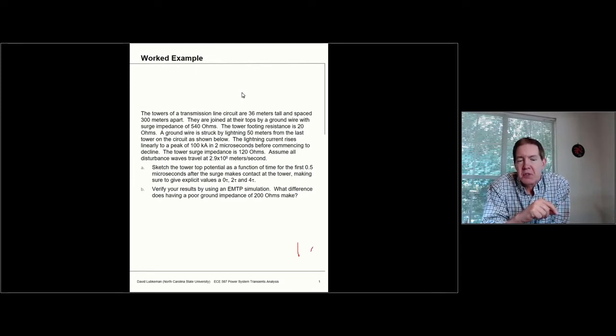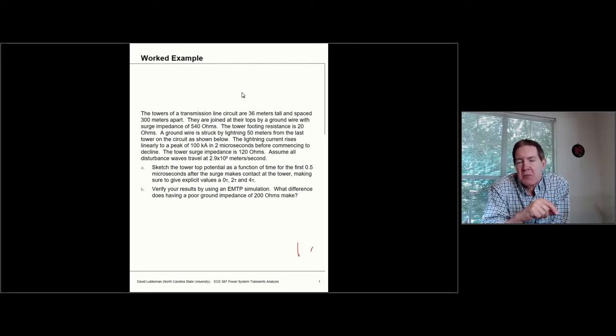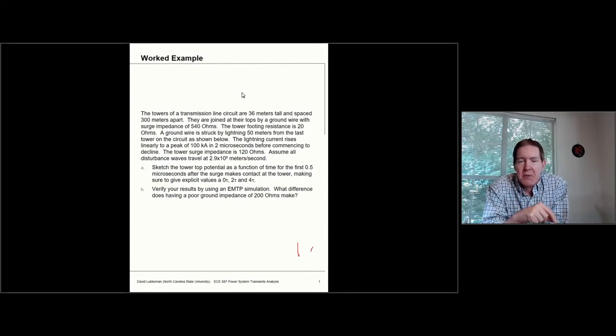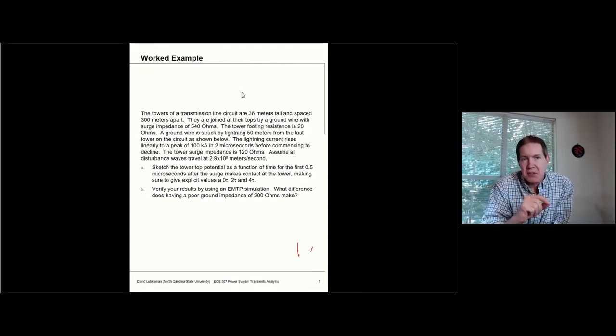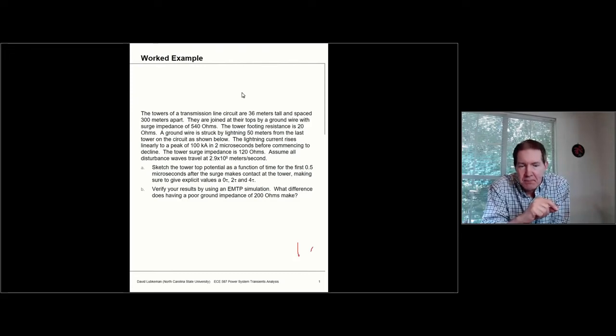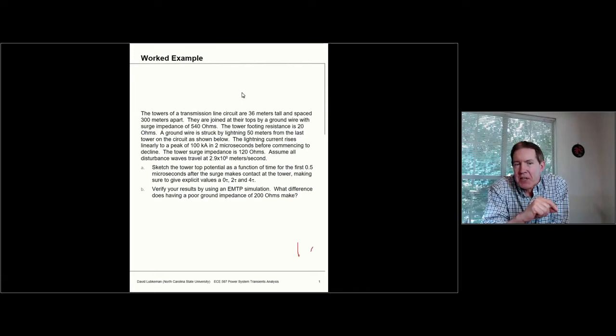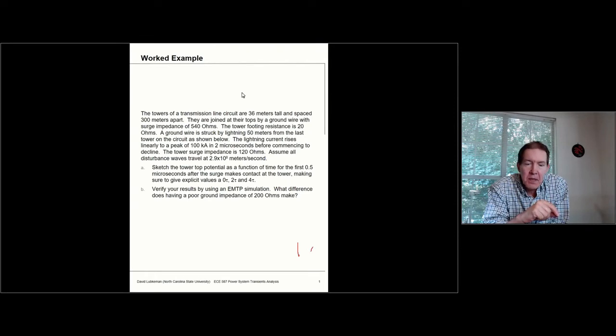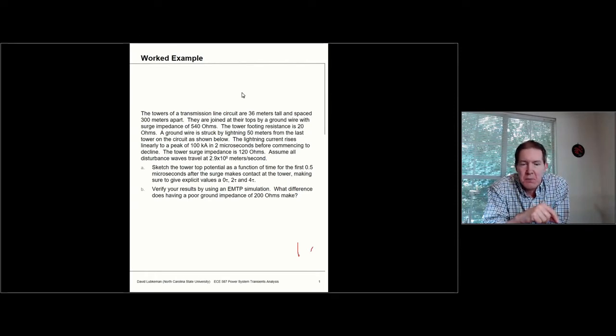We'll assume these disturbances travel at 2.9 times 10 to the 8 meters per second. For reference, the speed of light is 3 times 10 to the 8, so these waves travel slightly less than the speed of light. What I want to find out is what's going to happen to the tower top potential as a function of time — specifically for the first 0.5 microseconds, right after the surge makes contact with the tower.